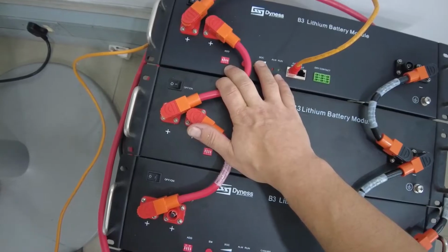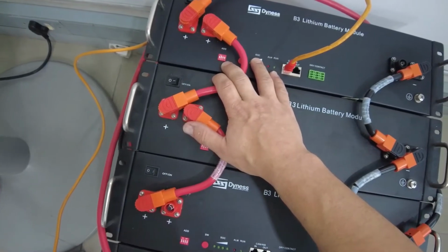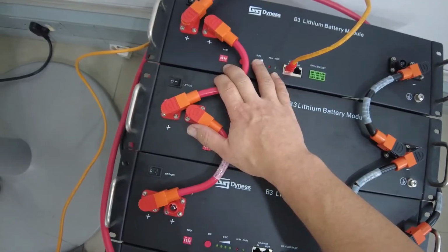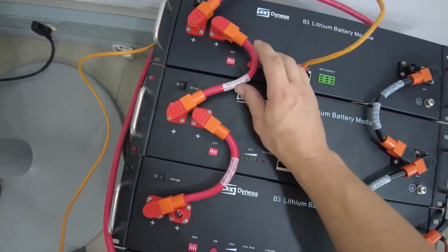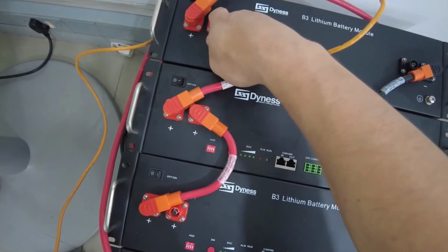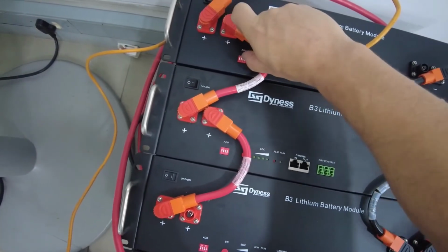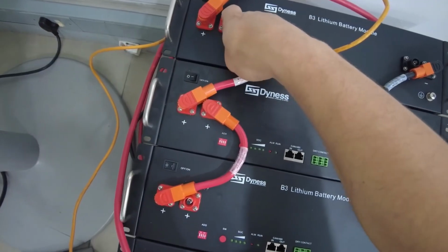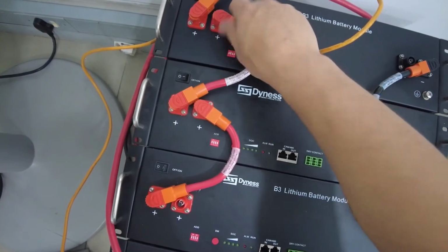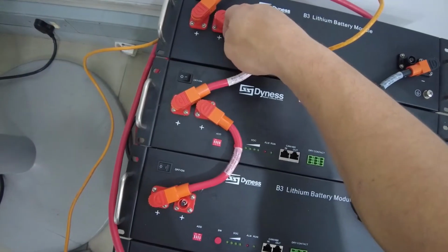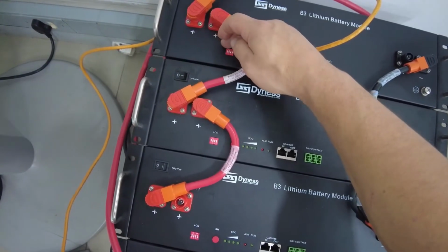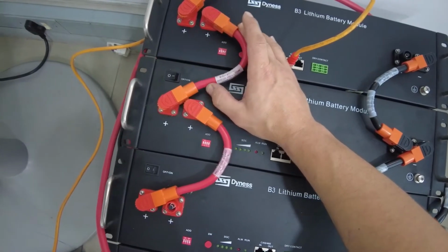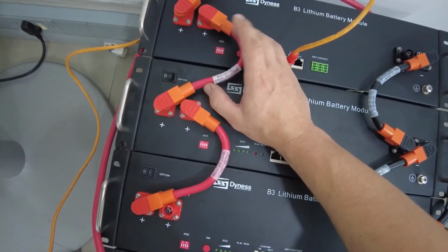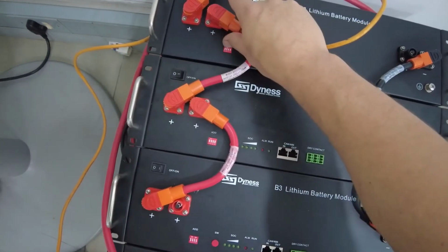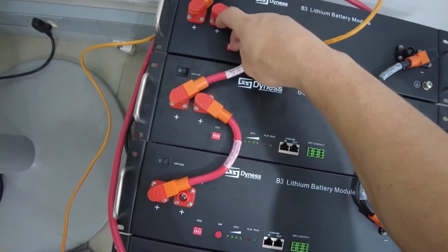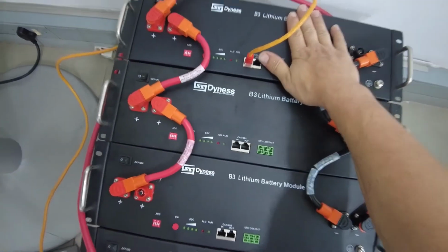Should you eventually struggle to find communication, where the inverter constantly gives you error 61, which is not detecting, it's good to take the dip switch and flick it back and forth, up and down, just so it makes contact again, and then reset it to your master setting. Again, as mentioned, for this King 5 kVA, dip 1 off, 2 on, 3 and 4 off. This is your master battery.